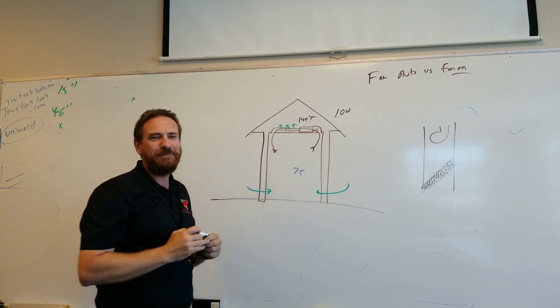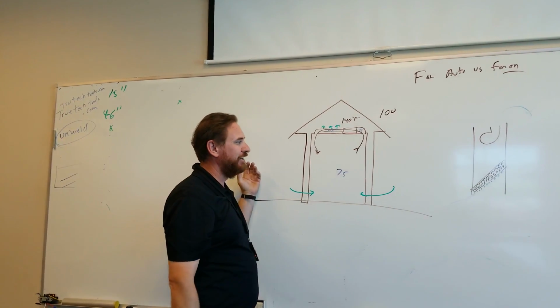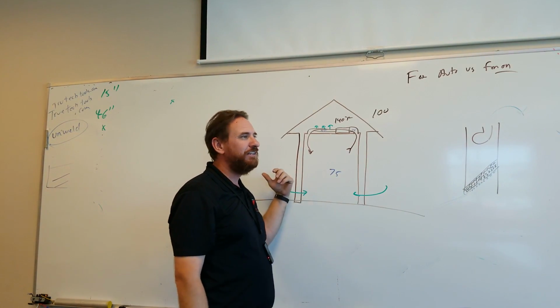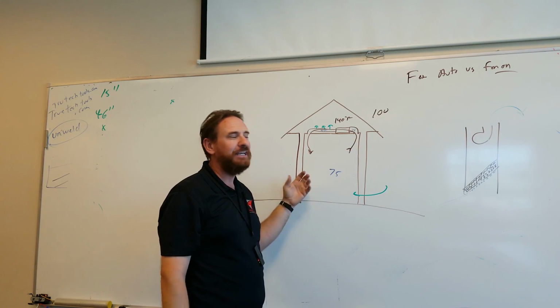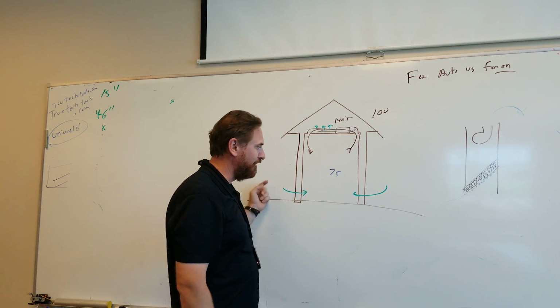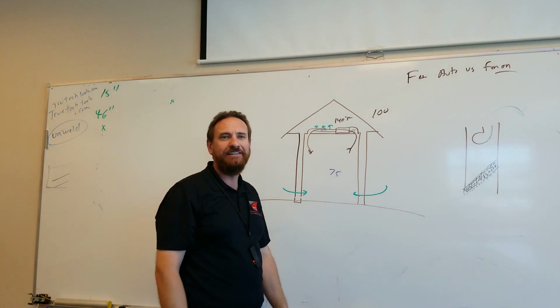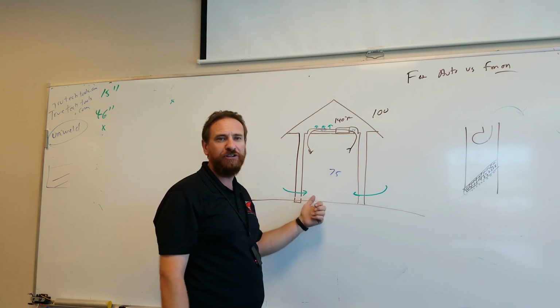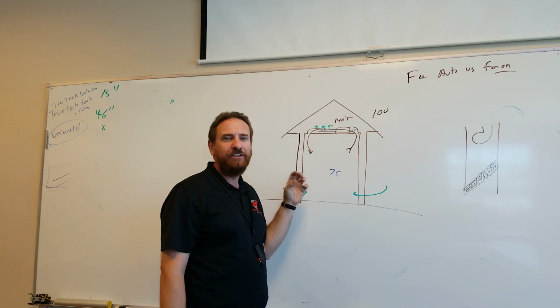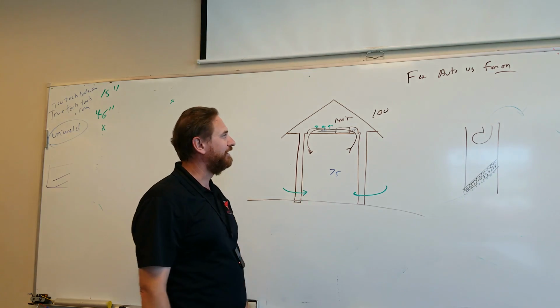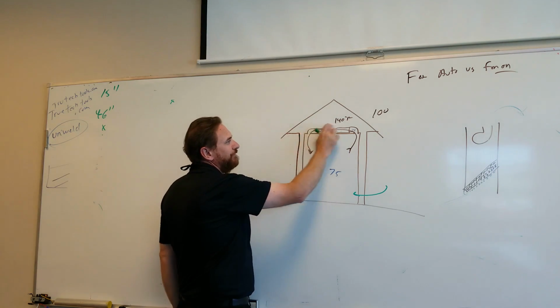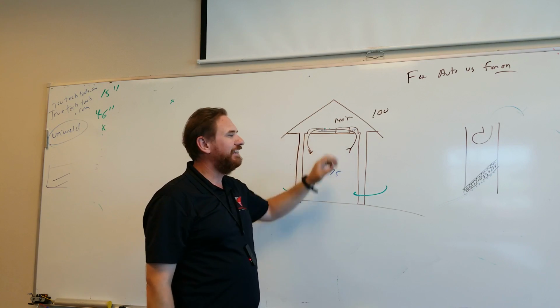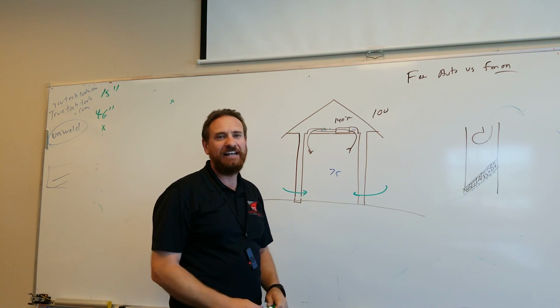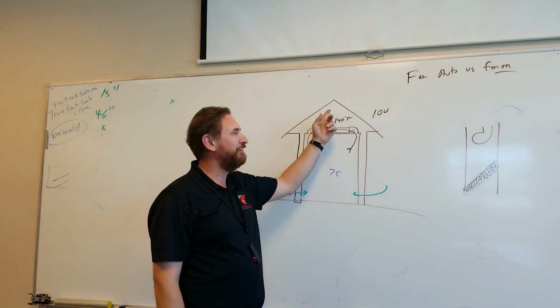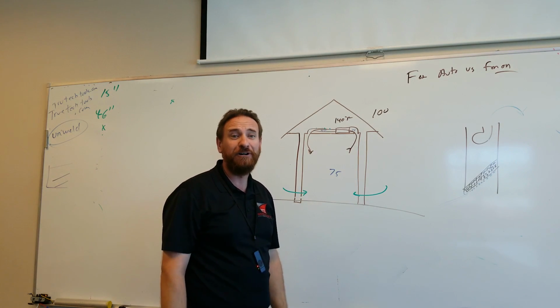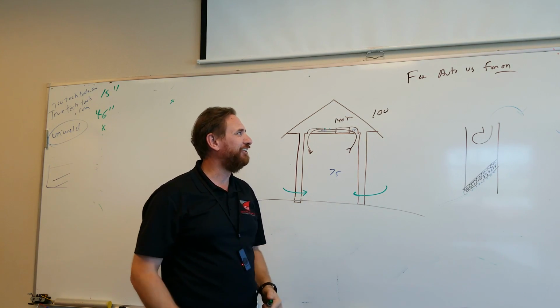As we're bringing air from outside in, we're also bringing in more polluted air, and we're bringing 100-degree air into this house, and that's going to be an issue. Through the doors, the windows, cracks in the ceiling, through plug outlets, anywhere it can pull air in. So we want to make sure those ducts are sealed, and ideally spending as least amount of time that air touching that hot attic air as possible, which is why attic ventilation also plays an important part of that as well. But we can keep going on this all day long.